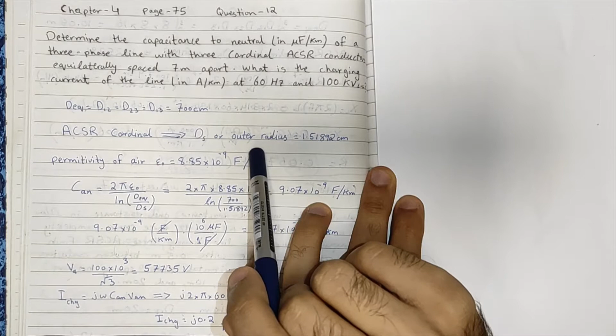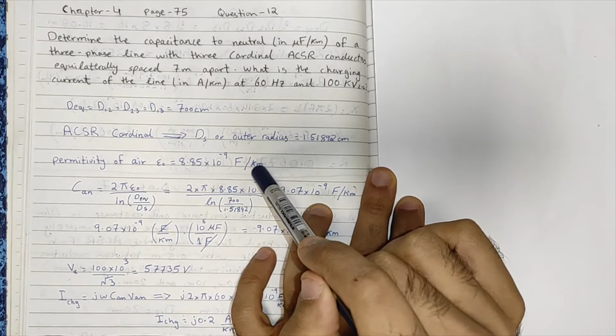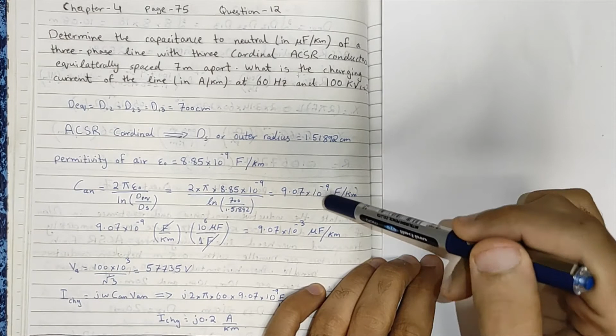The permittivity of air is epsilon naught, which is 8.85 multiplied by 10 to the power minus 9 farads per kilometer. And the formula that we will use to calculate the capacitance to neutral will be 2 pi epsilon naught over natural log of D equivalent over DS. By just substituting the values of all the variables and constants in this formula, we will get the capacitance to neutral to be 9.07 multiplied by 10 to the power minus 9 farads per kilometer.